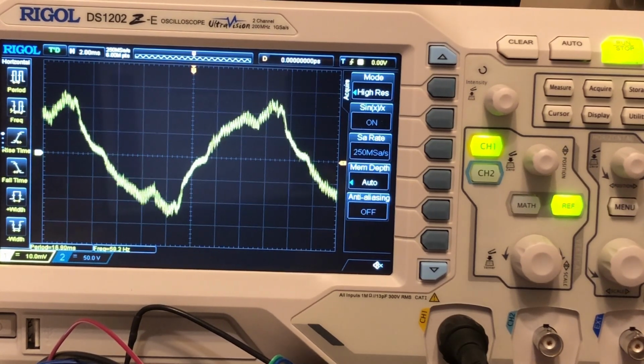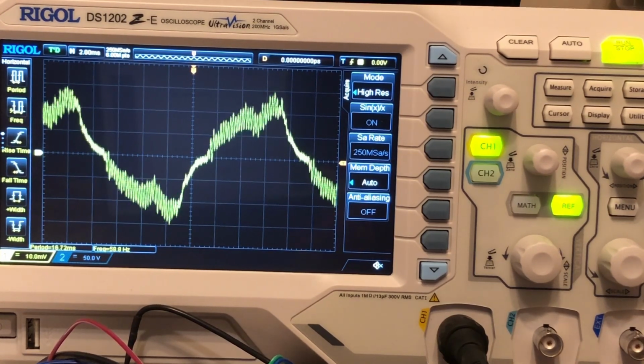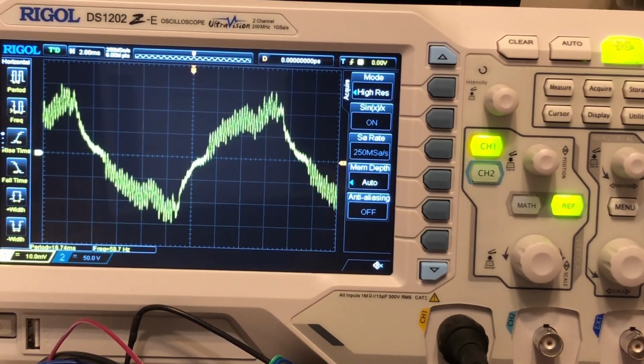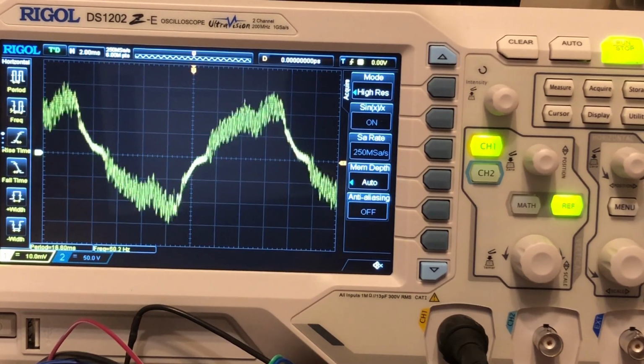Trigger settings should be based on the features of the input signal. Thus, you need to have some knowledge of the signal under test to quickly capture the desired waveform. This oscilloscope provides abundant advanced trigger functions which can help you to focus on the desired waveform details. The contents of this chapter: trigger source, trigger mode, trigger coupling, trigger hold-off, noise rejection, trigger type, trigger output connector. Trigger source. Press menu, then source, in the trigger control area on the front panel to select the desired trigger source.